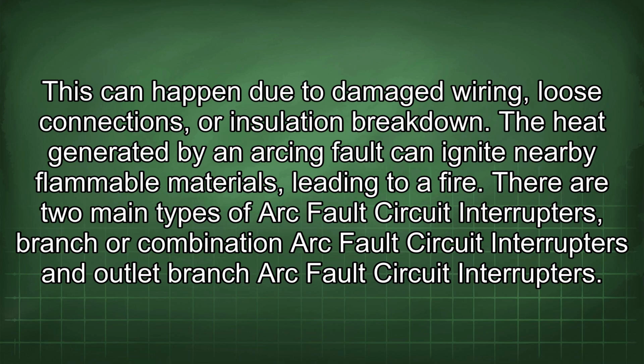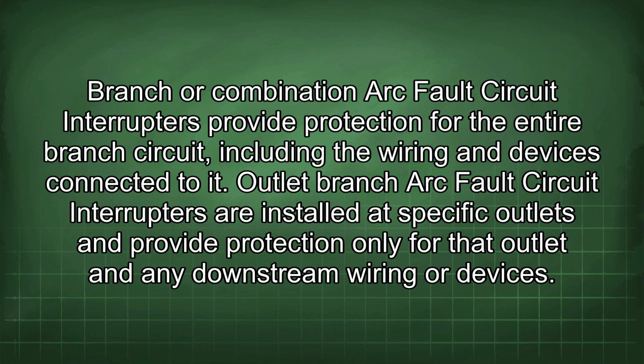There are two main types of arc fault circuit interrupters: branch or combination arc fault circuit interrupters and outlet branch arc fault circuit interrupters. Branch or combination arc fault circuit interrupters provide protection for the entire branch circuit, including the wiring and devices connected to it. Outlet branch arc fault circuit interrupters are installed at specific outlets and provide protection only for the outlet and any downstream wiring or devices.